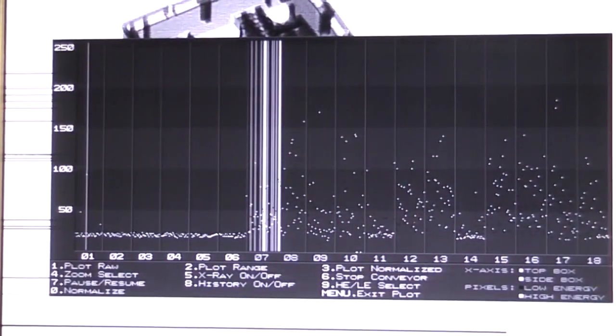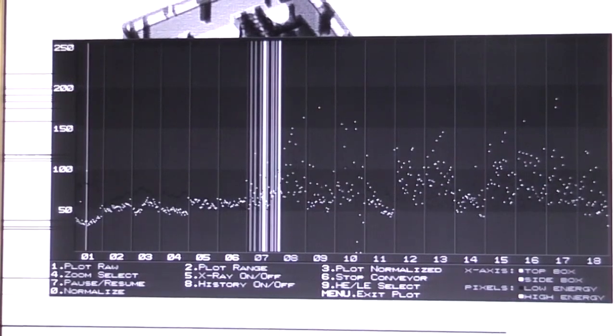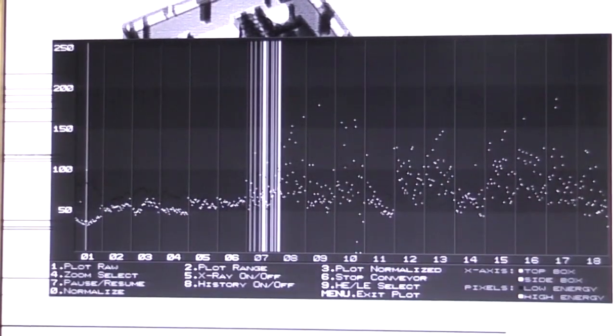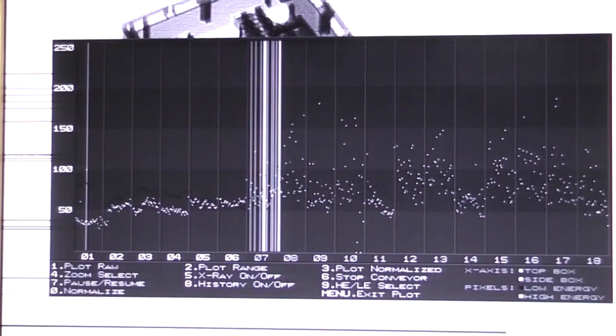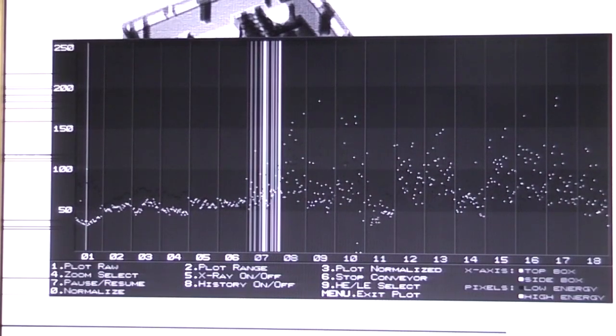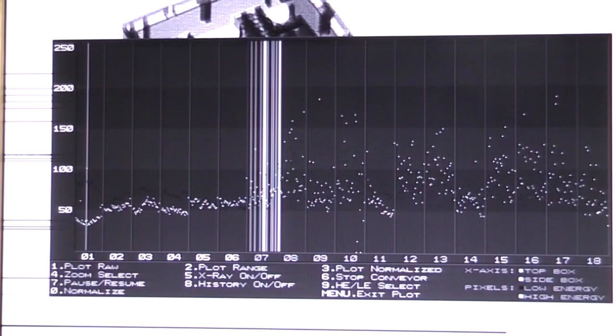One thing you can see quite clearly, if I turn the X-ray on, I'm going to wave a metal pipe across the sensors. If I start at the bottom of the back, we can see that's where the pipe is on the bottom sensors. I move up the back, and then along the top, you can see that although the sensors are high, they are still detecting, but they just seem to maybe have a very high dark current, or some issue with the whole data acquisition process.